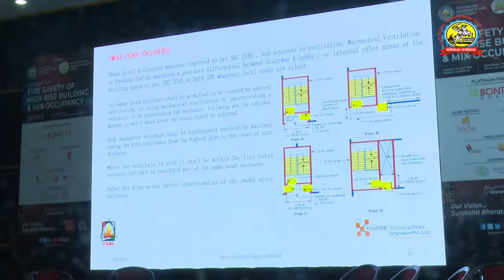Well, how do you protect it? You cannot put a pressurization system and give it to a residential building and tell the society to maintain it. They don't maintain the pump, so how will they maintain the pressurization system? Who is going to test it? So I asked them to pull the staircases to the perimeter of the building, and put a louver, just two louvers on the corner, so it is ventilated. Get a status of ventilation and that will suffice. You don't need to spend on a pressurization system that you then need to maintain.